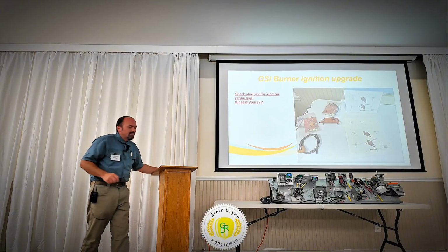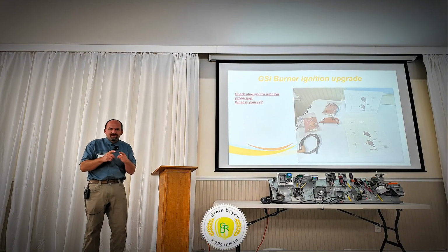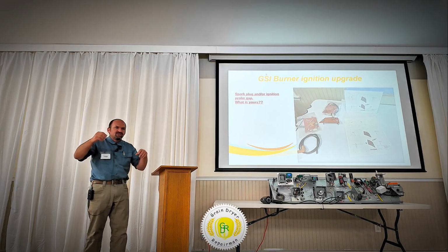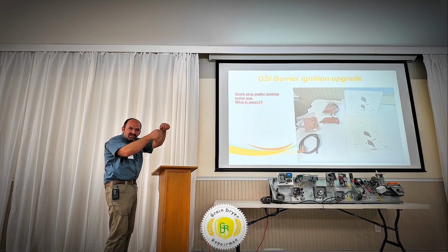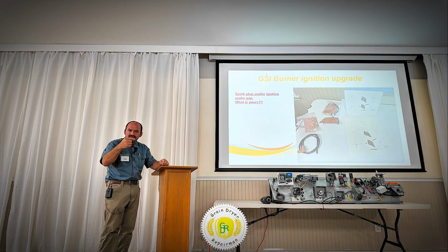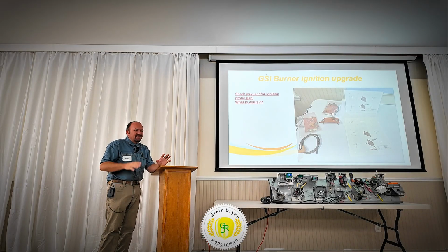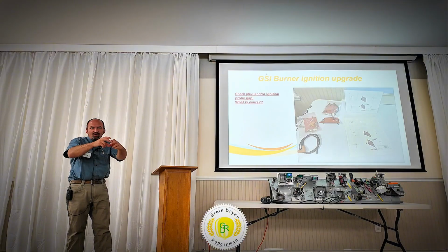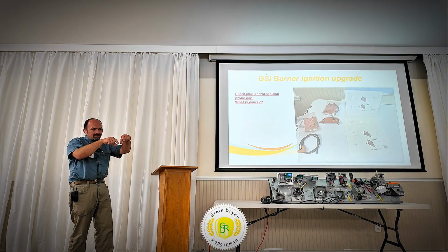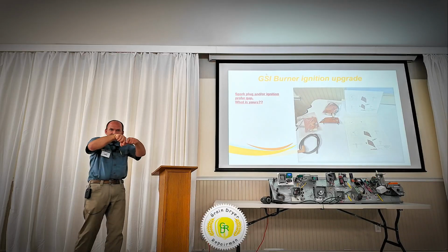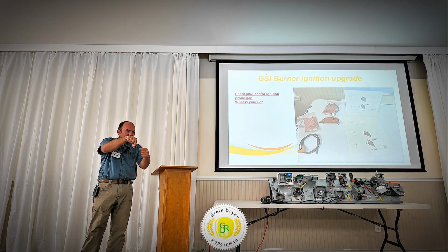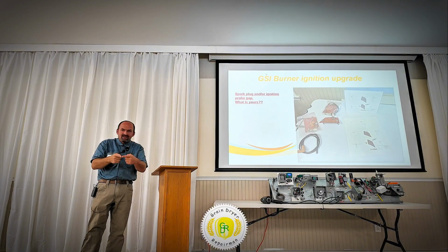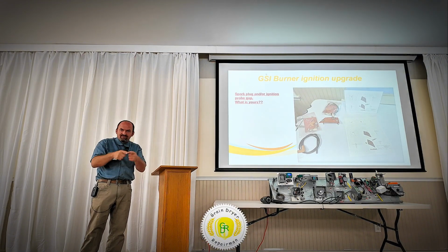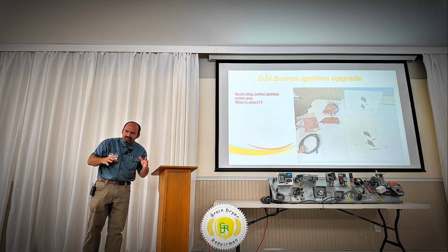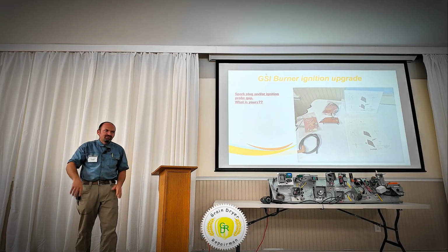Those flame probes, the ignition probes on GSI dryers, are a pain to reach in, especially from the side of the dryer, trying to adjust how close they are together. You try to bend them to get that 1/8 inch gap, using a screwdriver or something to check it. They can be a real pain. Or you can take the whole bracket out and adjust it, but then you need to make sure the ignition probes go through the hole correctly, not angled so one probe is closer to the edge of the hole than to the other probe, causing arcing to the housing instead of between the probes. That can be a real struggle if you've worked on them.